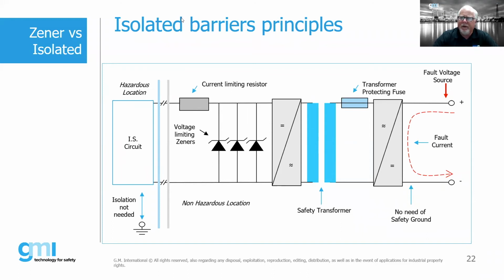So the use of an isolated barrier basically means, in effect, that we do not require the use of a dedicated IS earth, which answers some of the questions that people have asked about what's the big difference between an isolated barrier and a Zener barrier. That's the main difference. Obviously there's a difference in construction of the product itself, but the main thing from an application standpoint is that on an isolated barrier, you're not required to have that dedicated, intrinsically safe, clean earth. And that's probably the biggest advantage for using an isolated barrier versus a Zener type barrier.